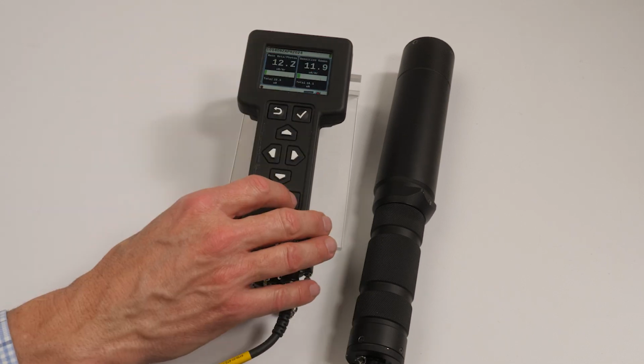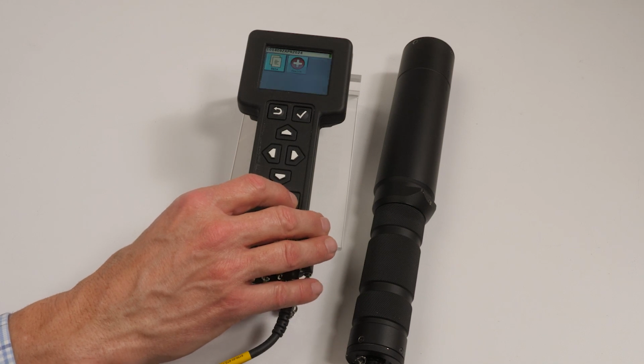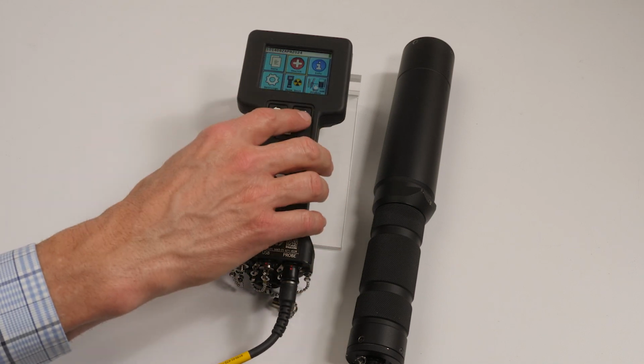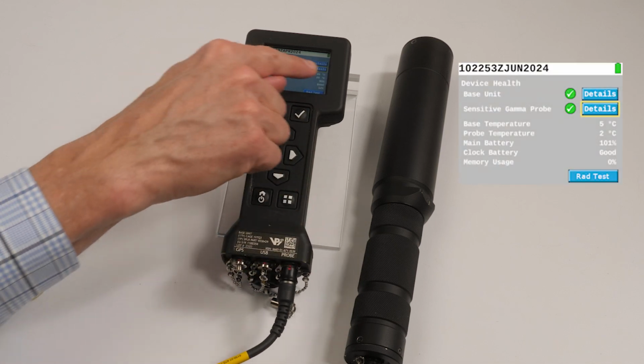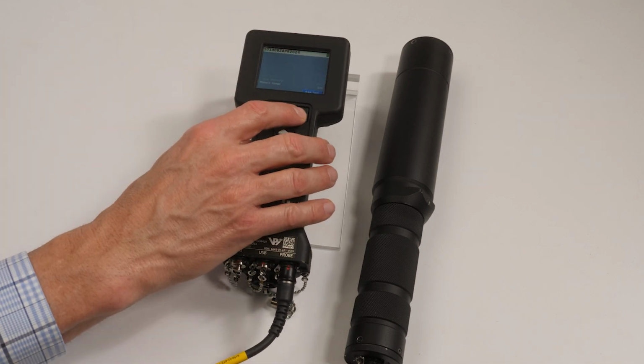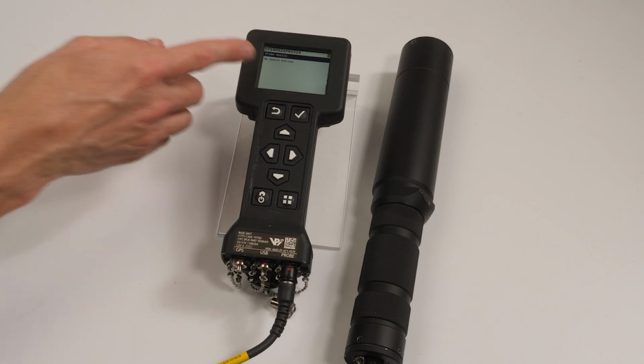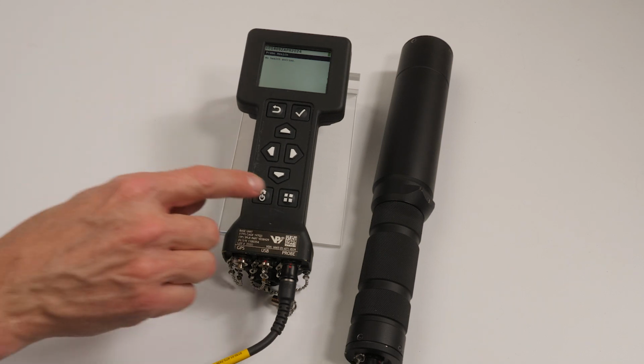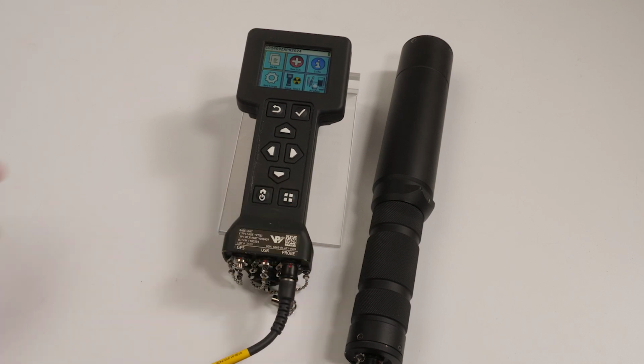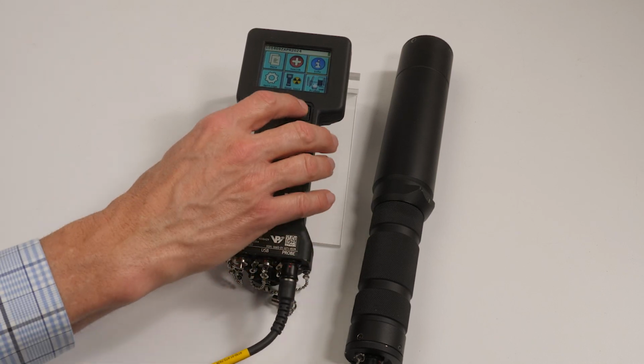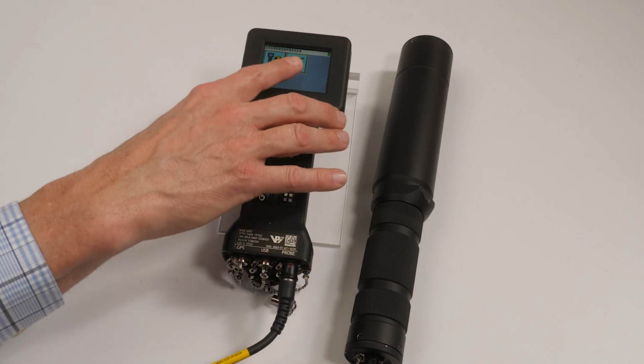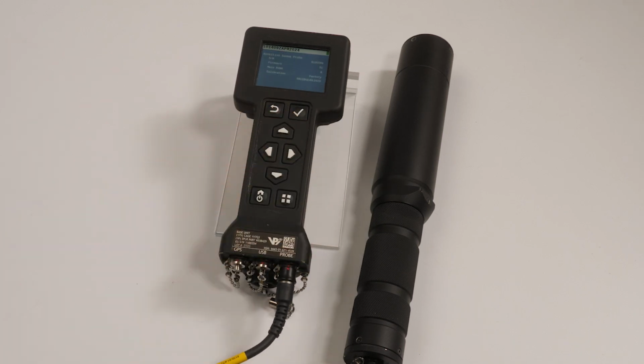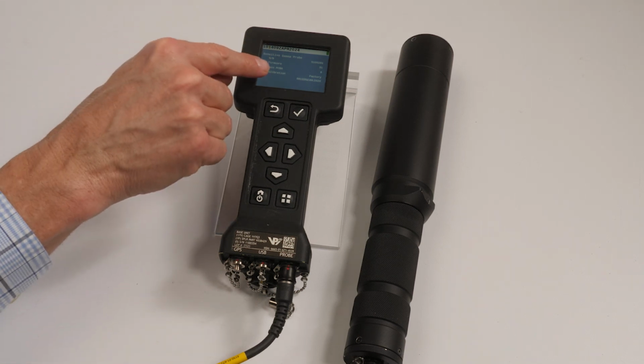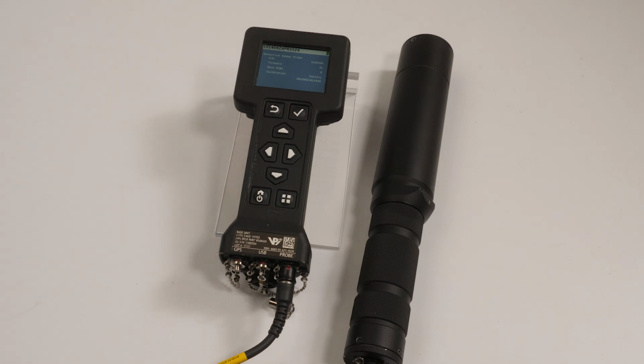To see the health status of the sensitive gamma probe, press the menu key, highlight Health, and press Enter. Press the down arrow key to highlight details for sensitive gamma probe, and press Enter. This screen displays current alarms, faults, and notifications if there are any. To view information about the sensitive gamma probe, press the menu key, highlight Info, and press Enter. Highlight the sensitive gamma probe icon and press Enter. On this screen, you can see the serial number of the probe, what firmware version is installed, the probe's main printed circuit board version number, calibration information, and date of calibration.